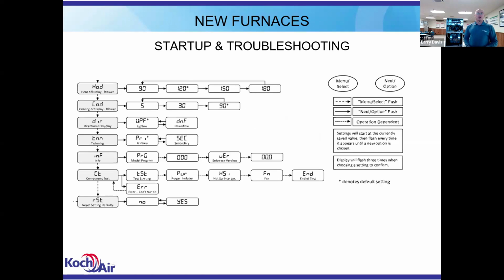All right. We looked at a little bit of that menu that we run through on the board a while ago. So here's some of the rest of it. When you're doing your startup and your setup, there's the HOD, that's your heating off delay, and a cooling off delay as well. You can change that. On the heating side, if you've got maybe a little tight ductwork, the fan's not running quite long enough, and you build up some heat and trip a limit, you can adjust that. Or the customer says, this thing's heat is great, but at the end of the heating cycle it gets a little drafty, so you slow it down a bit. Same thing on the cooling. You don't want to run too long and evaporate all the moisture off your coil.